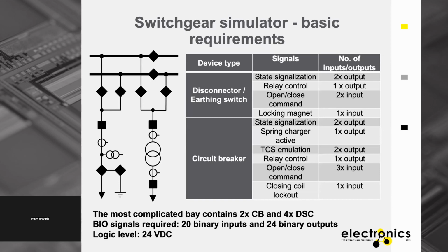Here is the presentation of basic requirements for the simulation of the switchgear. We have basically 2 main feeders: the transformer feeders and the power line feeders. Here are some signals and input-output requirements. The most complicated bay is for the transformer. It consists of 2 circuit breakers and 4 disconnectors, and here is a representation of signals connected to each specific switching device.